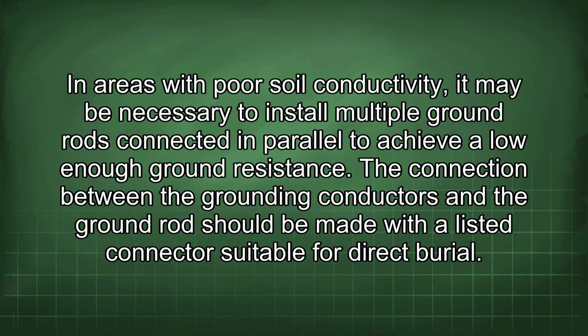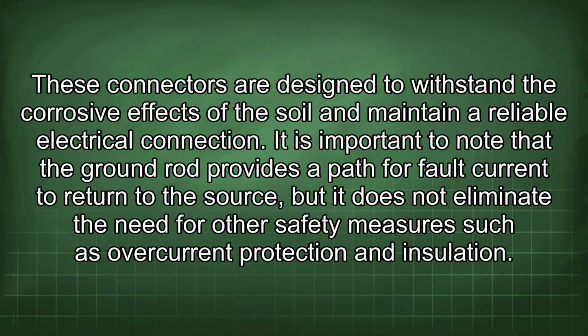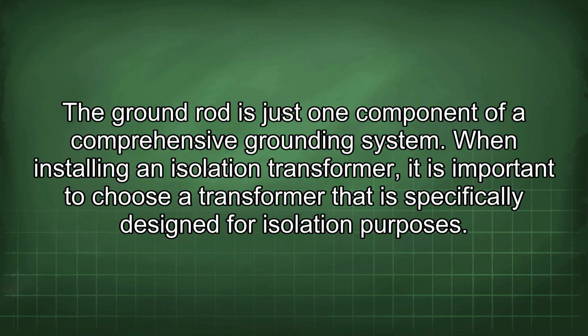In areas with poor soil conductivity, it may be necessary to install multiple ground rods connected in parallel to achieve a low enough ground resistance. The connection between the grounding conductors and the ground rod should be made with a listed connector suitable for direct burial. These connectors are designed to withstand the corrosive effects of the soil and maintain a reliable electrical connection. It is important to note that the ground rod provides a path for fault current to return to the source, but it does not eliminate the need for other safety measures such as overcurrent protection and insulation. The ground rod is just one component of a comprehensive grounding system.